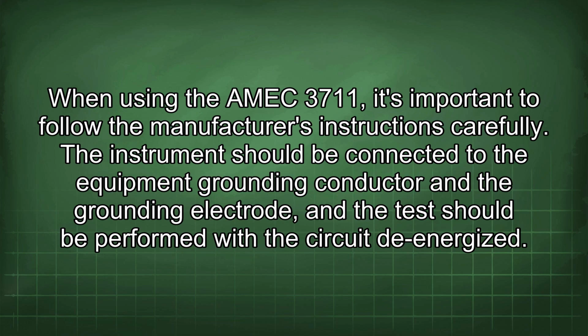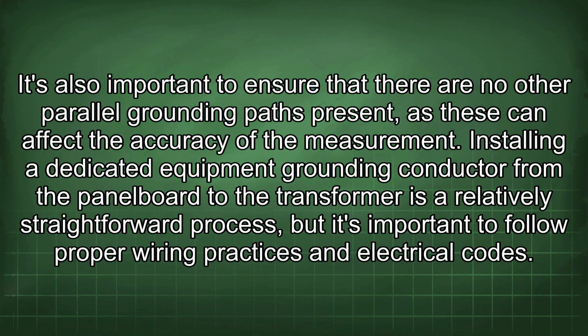When using the AEMC 3711, it's important to follow the manufacturer's instructions carefully. The instrument should be connected to the equipment grounding conductor and the grounding electrode, and the test should be performed with the circuit de-energized. It's also important to ensure that there are no other parallel grounding paths present, as these can affect the accuracy of the measurement.